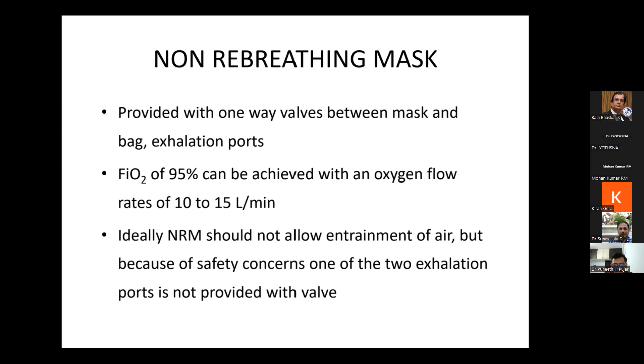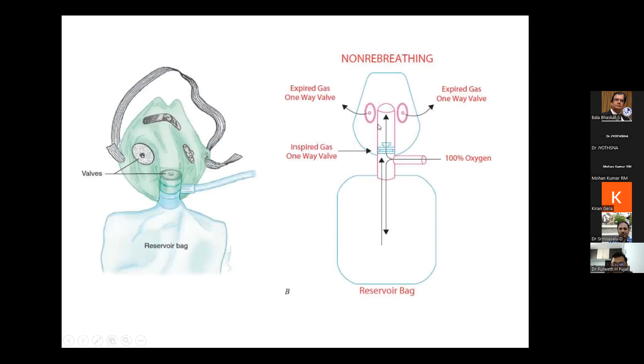What happens here? Here between the face and the mask, we have the valve, and in the exhalation ports also we have valves. Because of safety concerns, one of the exhalation valves will be absent. So coming to here, the higher oxygen supply rates are required. Desirable in cases where rebreathing of carbon dioxide would be detrimental, that is in case of head injury patients.